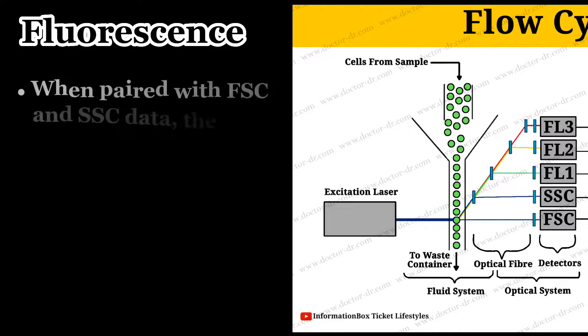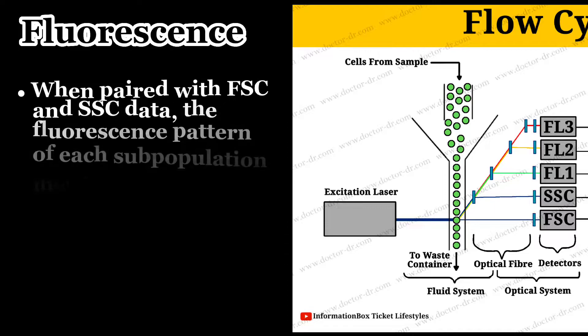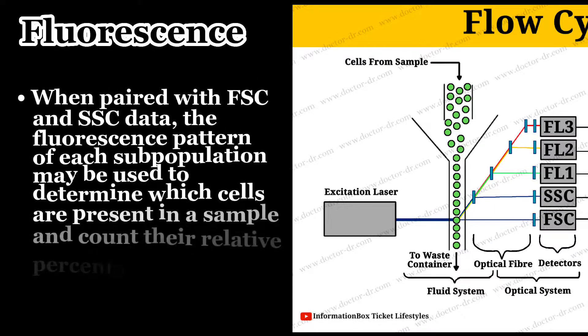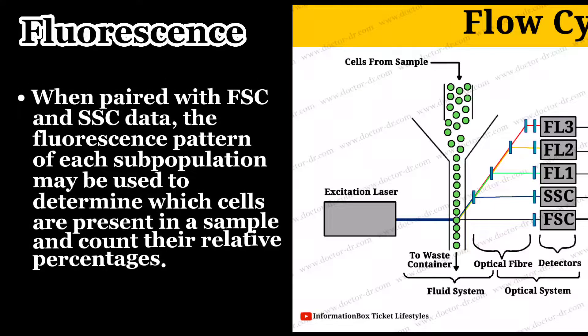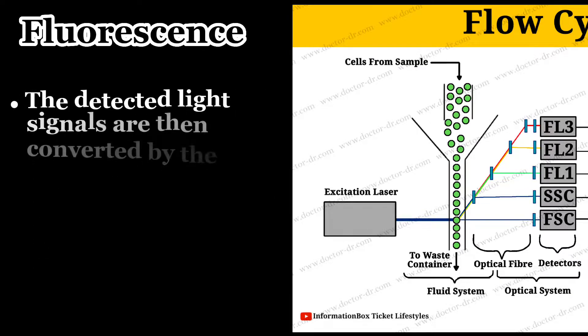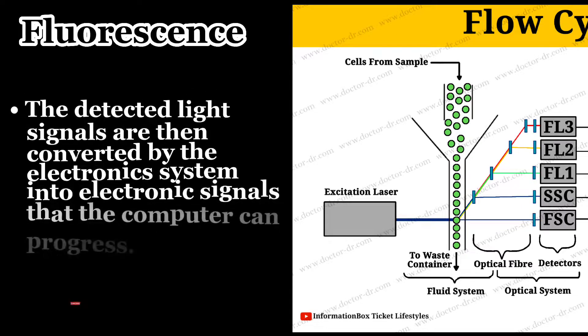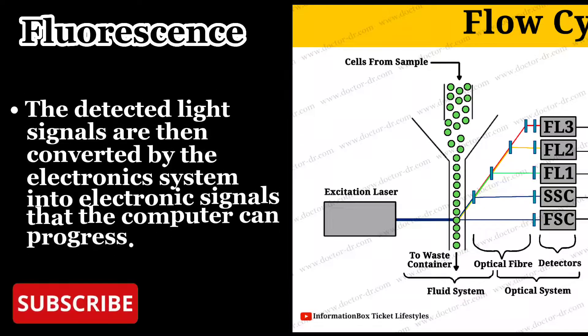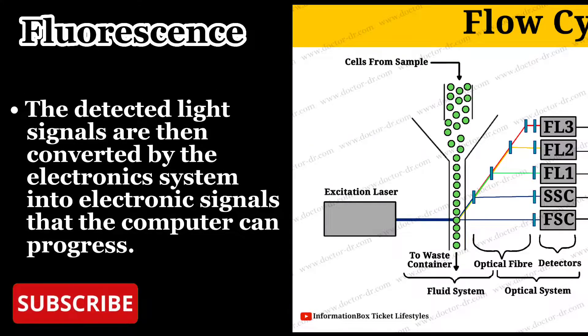When paired with forward scattered light and side scattered light data, the fluorescence pattern of each subpopulation may be used to determine which cells are present in a sample and collect their relative percentages. The detected light signals are then converted by the electronic system into electronic signals that the computer can process.